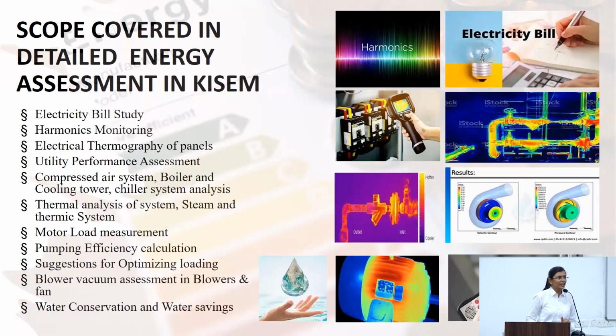Next thing is the cooling tower and chilled water system. In the chiller we examine what the flow in the evaporator is, or what the actual TR generation is with respect to the rated TR, and for generating that actual TR, how much power the compressor is consuming. We also examine the condenser health as well as the evaporator health, so that we can understand the complete profile of the chiller system, and why the power consumption is increasing. By doing these things, we are able to understand why the chiller performance is not good. Similarly, for the cooling tower, we also examine the cooling tower performance and all these things.